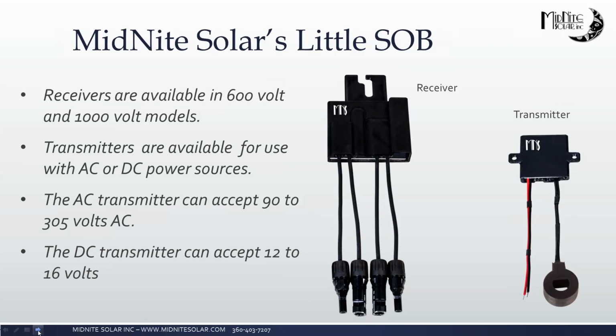There's no cabling between the ground and the PV array. It's all done, as Sue mentioned, through PLC, which is a power line carrier signal that rides on top of the DC current. And the receiver's up there listening to it. It's sort of like a radio transmitter and receiver, almost like in your car. Very easy to install, and basically an AC power outage or shutting down the inverter with the AC disconnect is going to trigger your rapid shutdown, making it very easy for the firefighters.